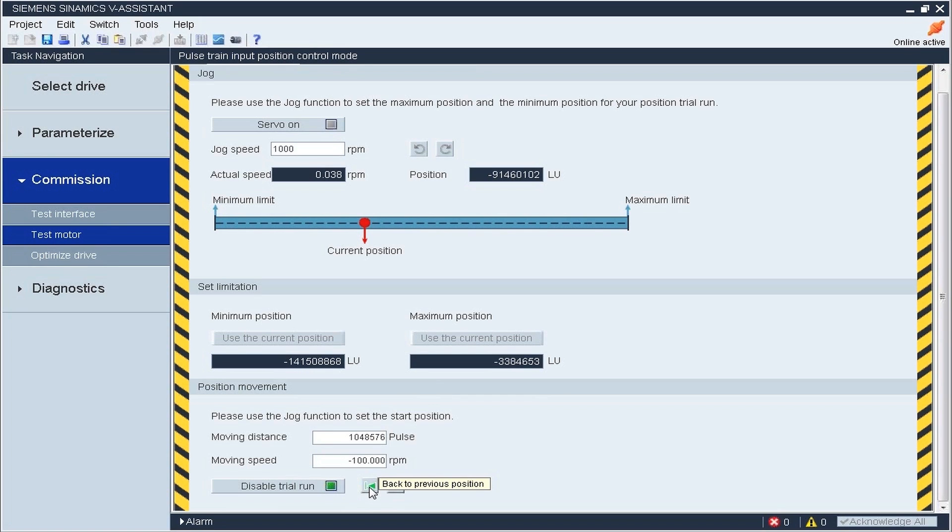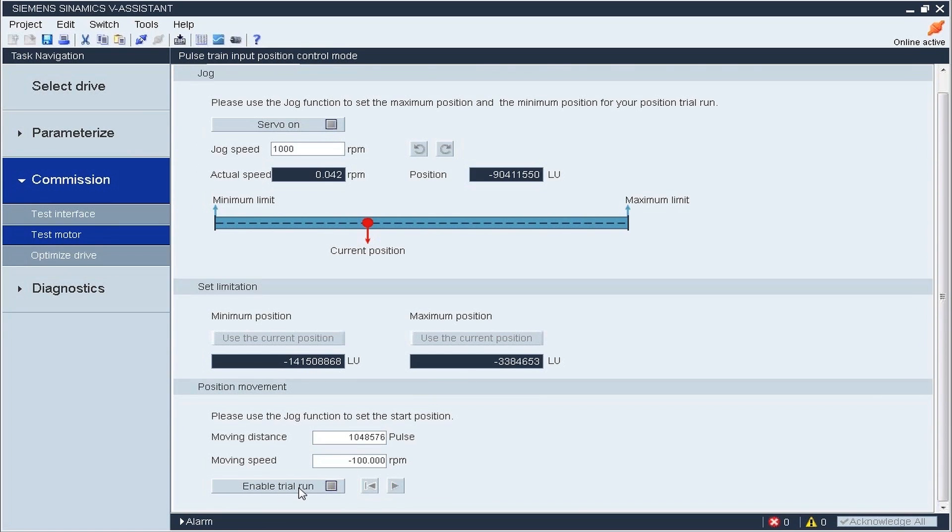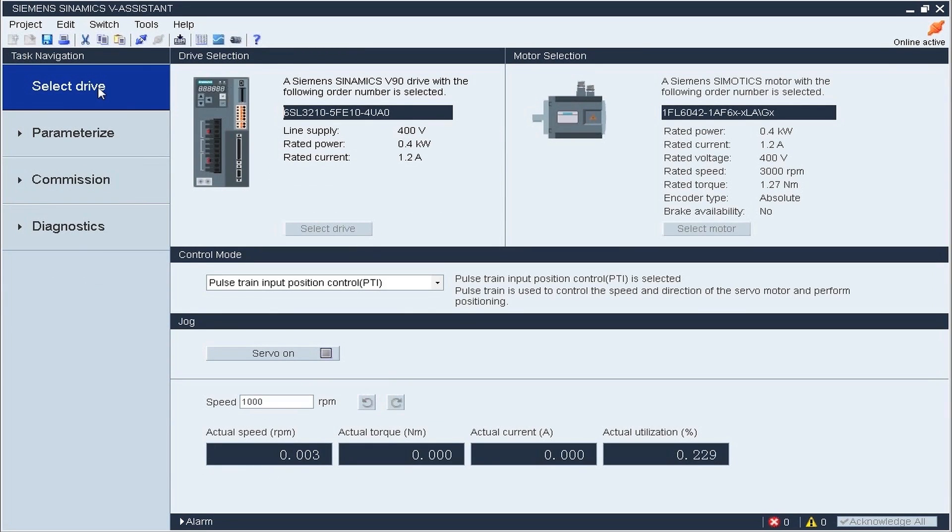Click on the START TRIAL RUN button and the motor will run. If you want to go back to PREVIOUS POSITION, please press BACK to PREVIOUS POSITION button. After finishing the operation, please withdraw the TRIAL RUN signal. Then go OFFLINE to FINISH ALL OPERATION.